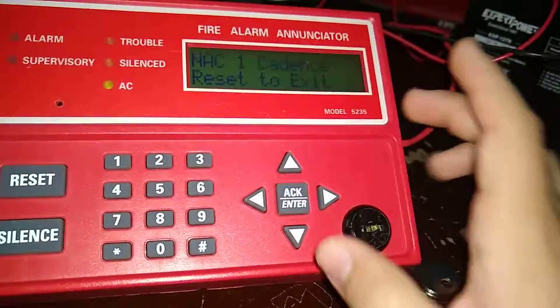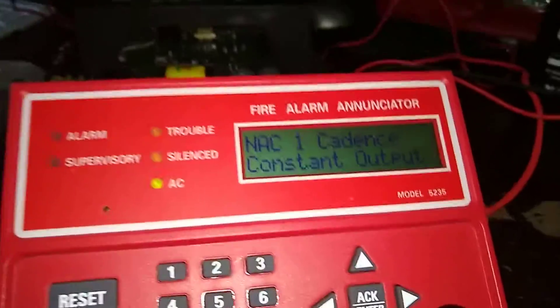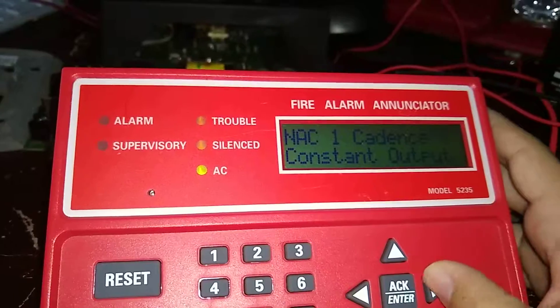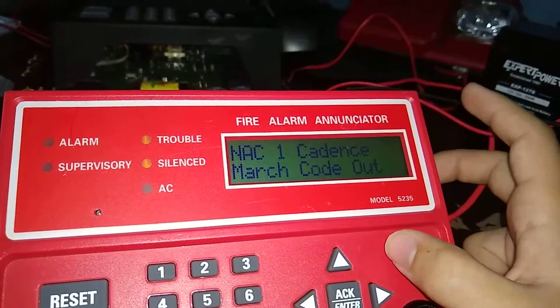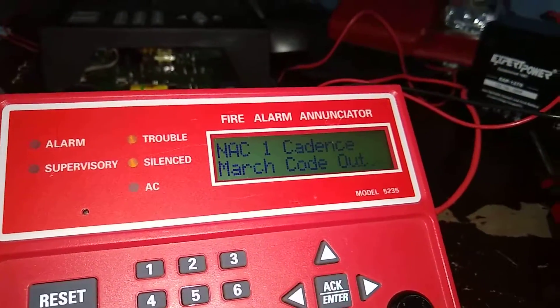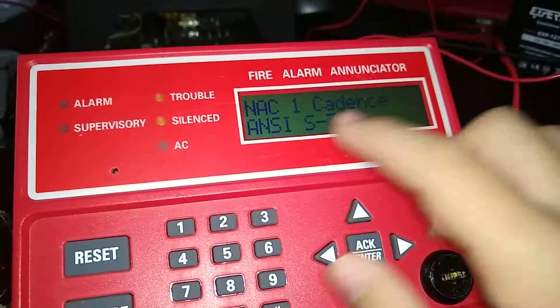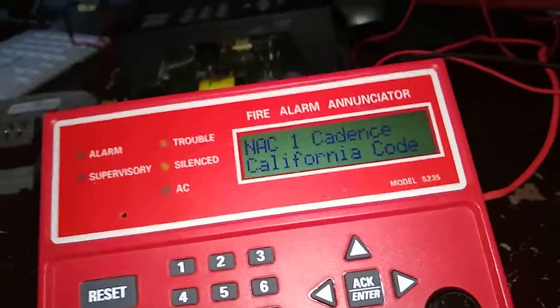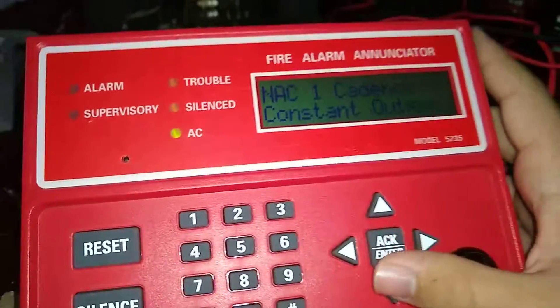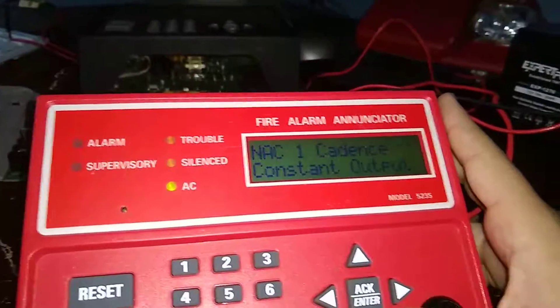NAC one cadence — that would be your coding options. For some reason this panel will only let me scroll through: constant output, which is continuous; march code, which is pulsing like code three but pulsing; then there's this option which would be code three; single stroke; California code — not a hundred percent sure what that is; and constant output. I just have mine set to constant output. There should be synchronization options but nothing on here.